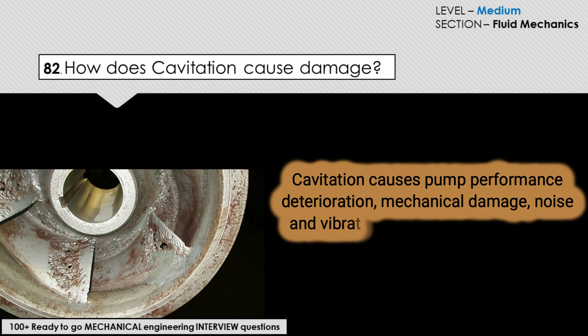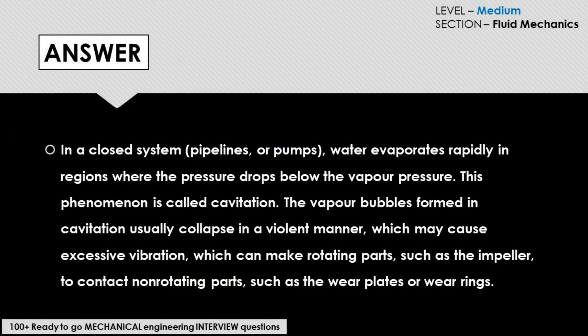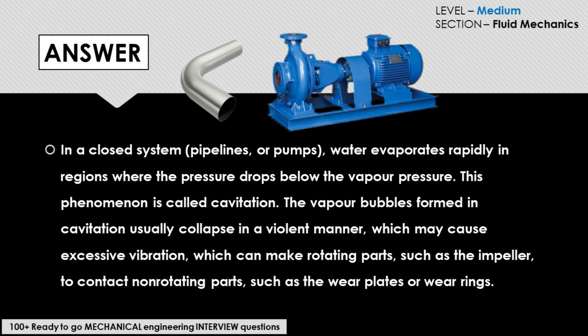How does cavitation cause damage? Cavitation causes pump performance to deteriorate; there will be mechanical damage, noise, and vibration, which can ultimately lead to the failure of the pump. Vibration is a common symptom of cavitation and many times the first sign of an issue. Vibration causes problems for many pump components including the shaft, bearings, and seals.